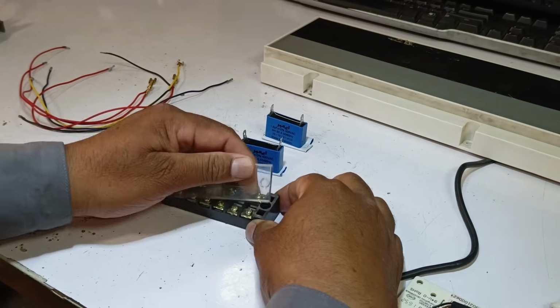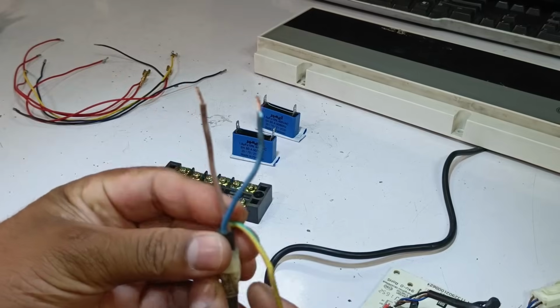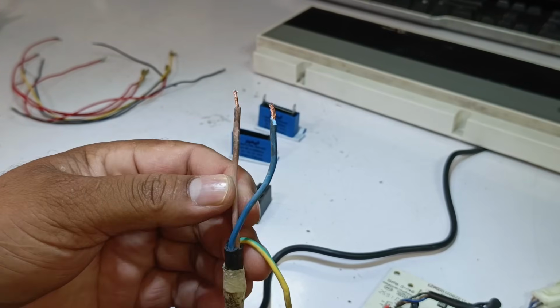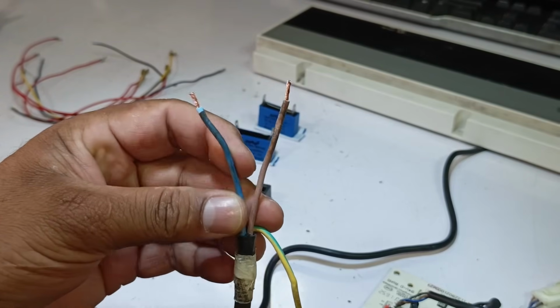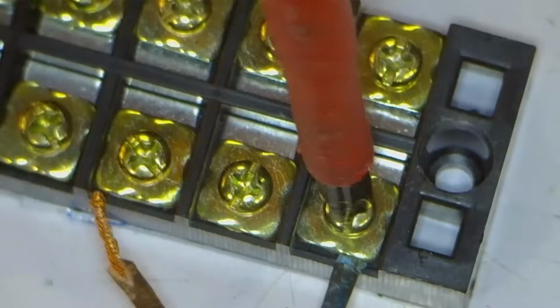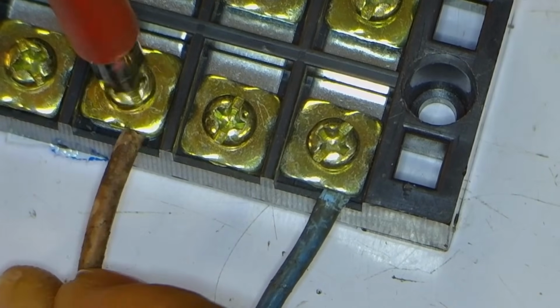I'll remove the cover of the connector. Here I have 2 wires. This is my main single-phase supply, and using it, I'm going to create a 3-phase supply. First, I'll connect the blue wire to the connector. Then, I'll connect the second wire, leaving one point of the connector free. So now, the line and neutral wires for the single-phase supply are connected.